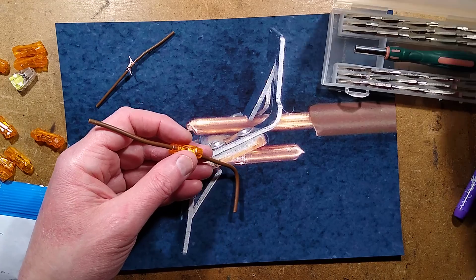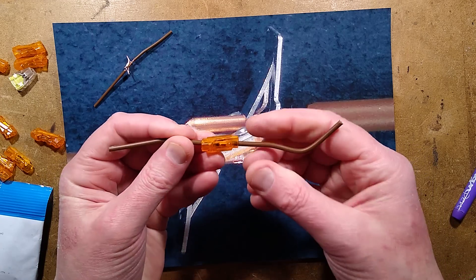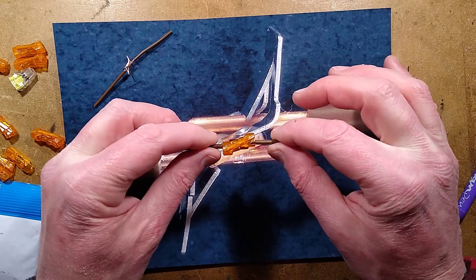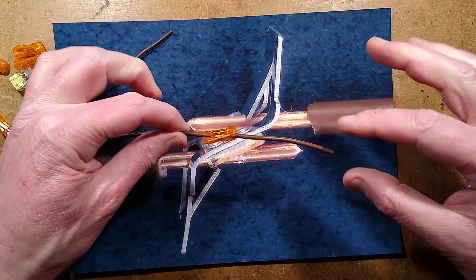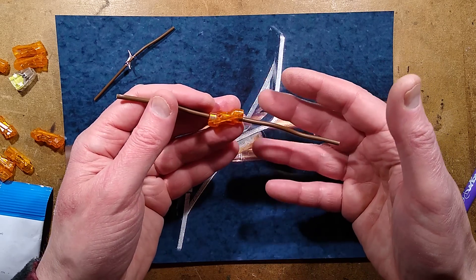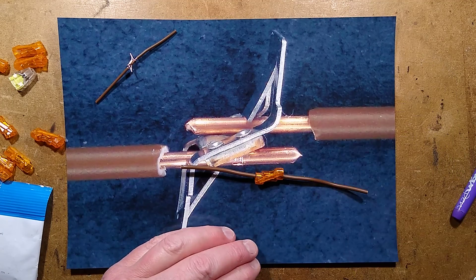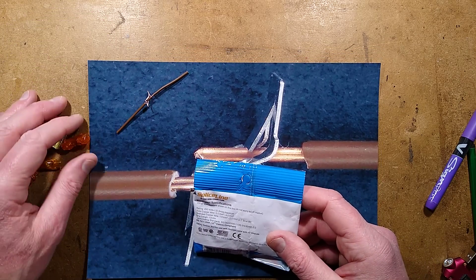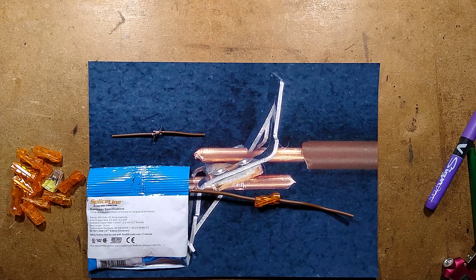Is there much else really to say about these? They seem to be sensibly designed. It's quite nice that the cables only have to overlap a small section — if a cable got cut you only need a little bit of slack to strip and push into this connector. It has that straight-through flow with the cable coming in one side and out the other, and as they say it could be used to extend cables when a cable has been left a bit short in a switch or socket box. It's a neat, nice-looking connector — an interesting alternative to the WAGO connector and it does seem to work quite well.